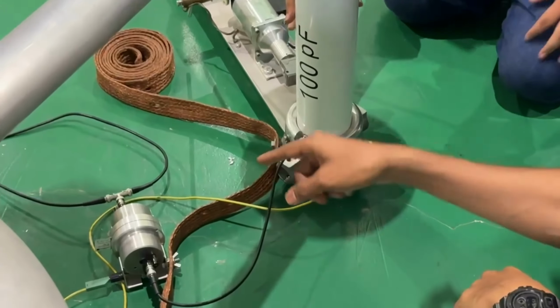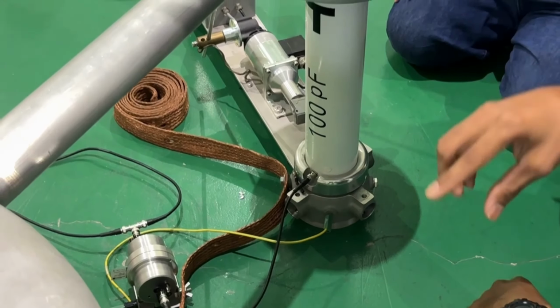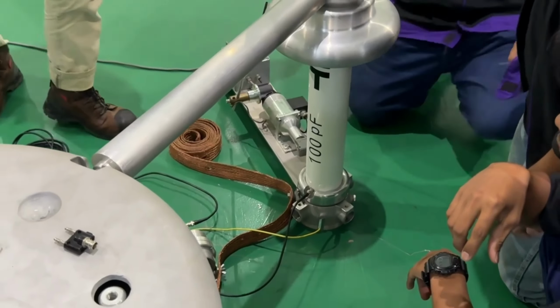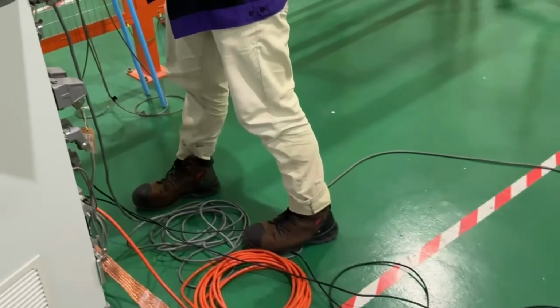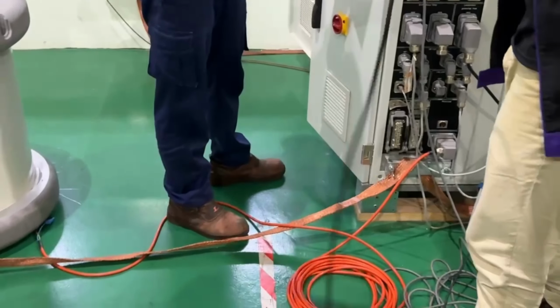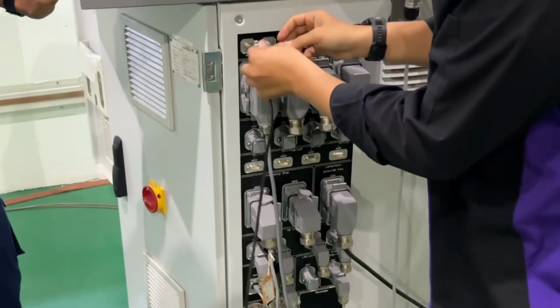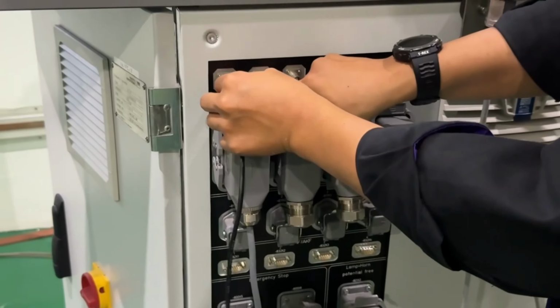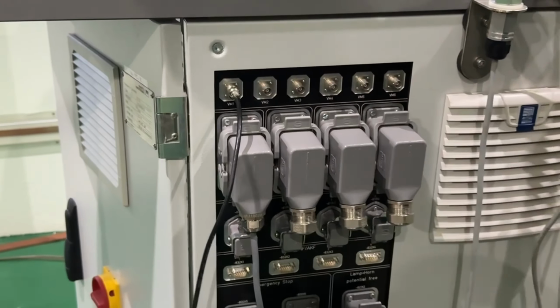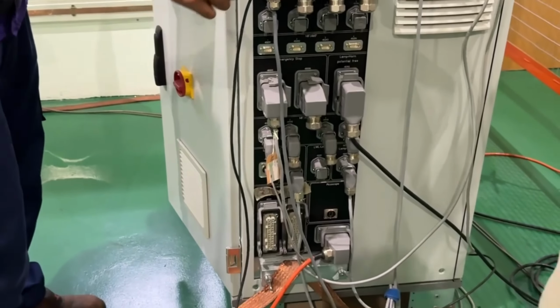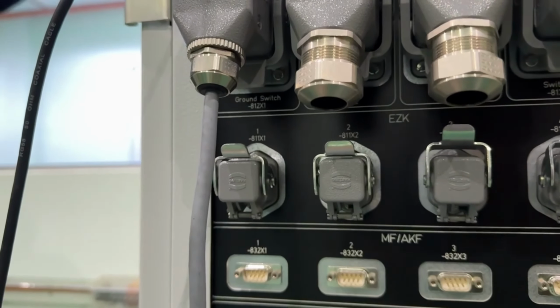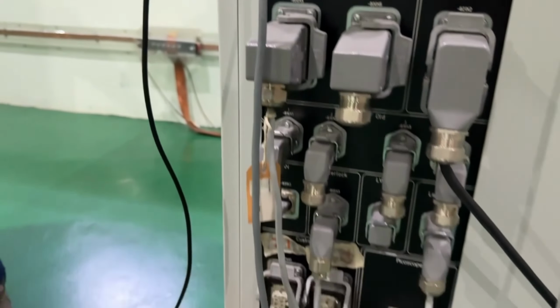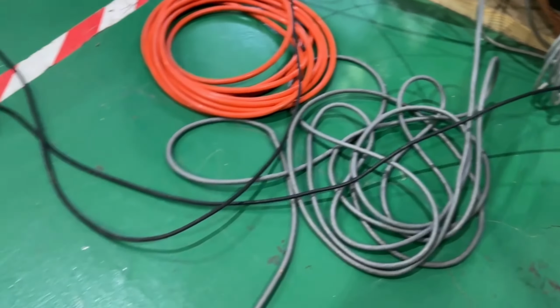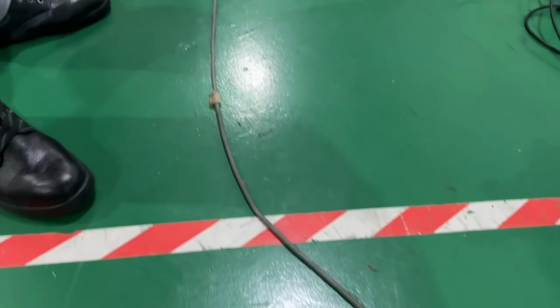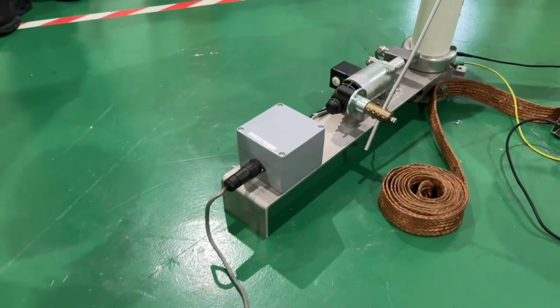At the second port of the CB impulse, insert another black connector. Connect a T-junction fitting to this black connector. Connect one coaxial cable from the control room and another from the frequency converter to the T-junction. The end of the FC coaxial cable will be connected to channel 1 of the frequency controller. Last but not least, ground the frequency controller. Connect a ground switch for the frequency controller unit and ensure this switch is properly grounded to protect the system.